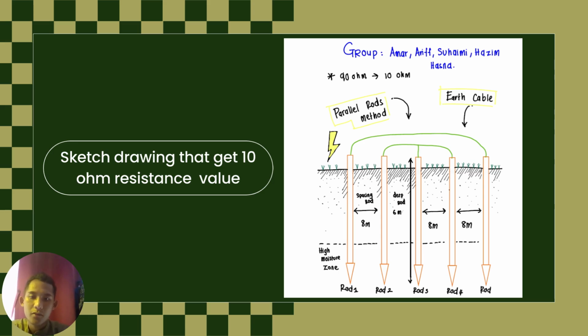So as you can see, this is a sketch drawing that will get 10 ohm from the 90 ohms resistance. There are 5 copper rods, and we will put them 6 meters deep underground until they enter the higher moisture zone, because higher moisture is very good for getting lower resistance. We put them in parallel position because parallel is more effective to get lower resistivity. The green line is the earthing cable. For the spacing of the rods, we put 8 meters because we want the rods to cover the higher zone, so make sure the covered area is increased.